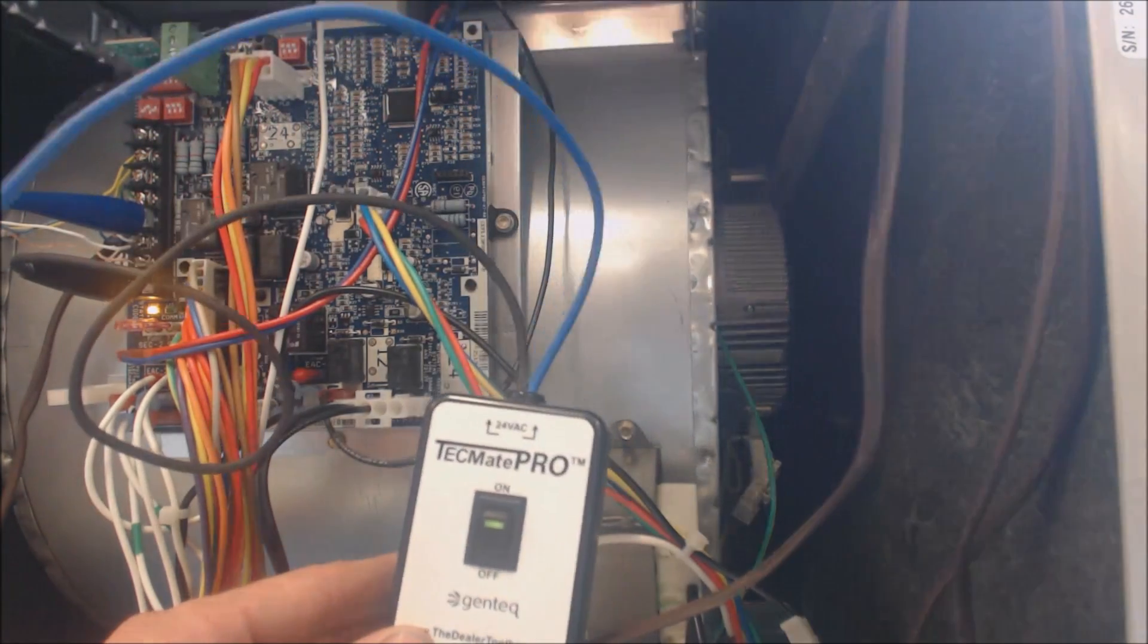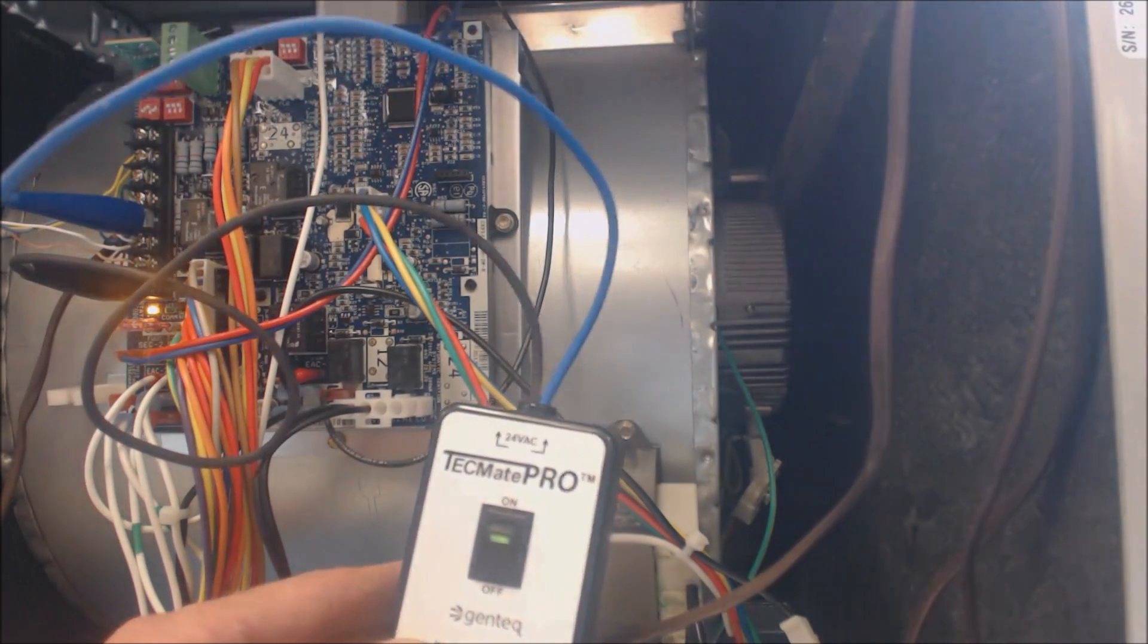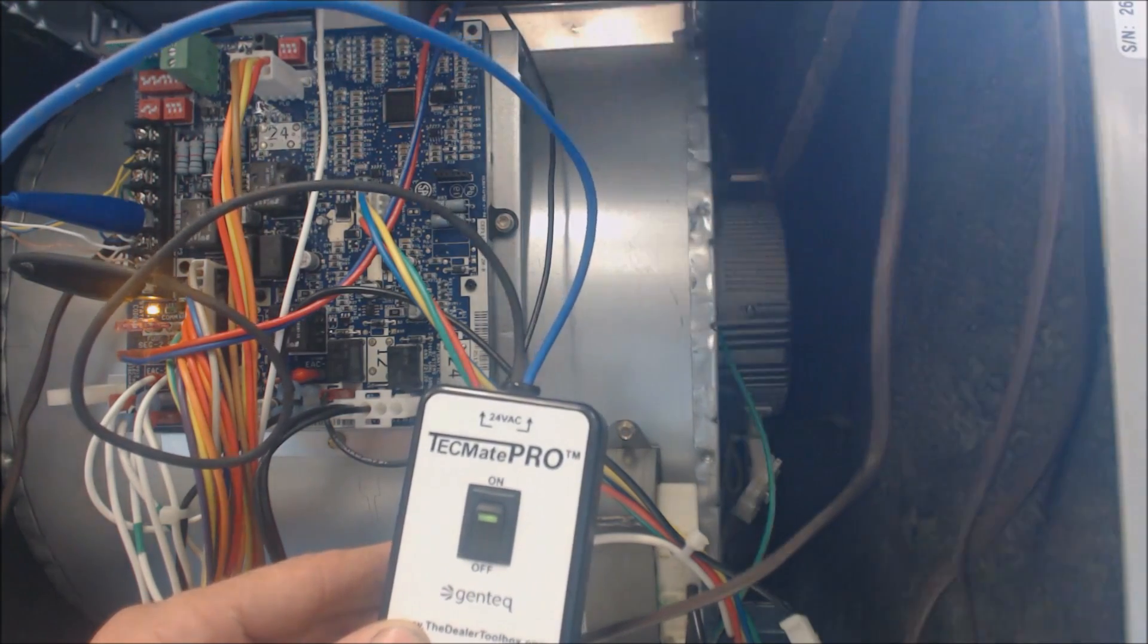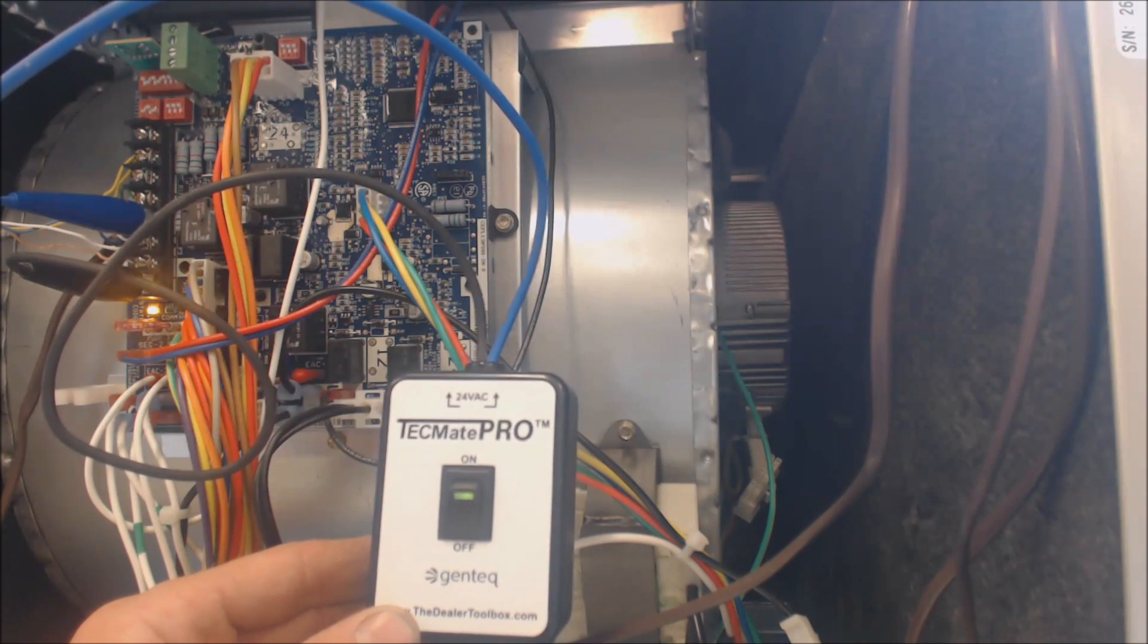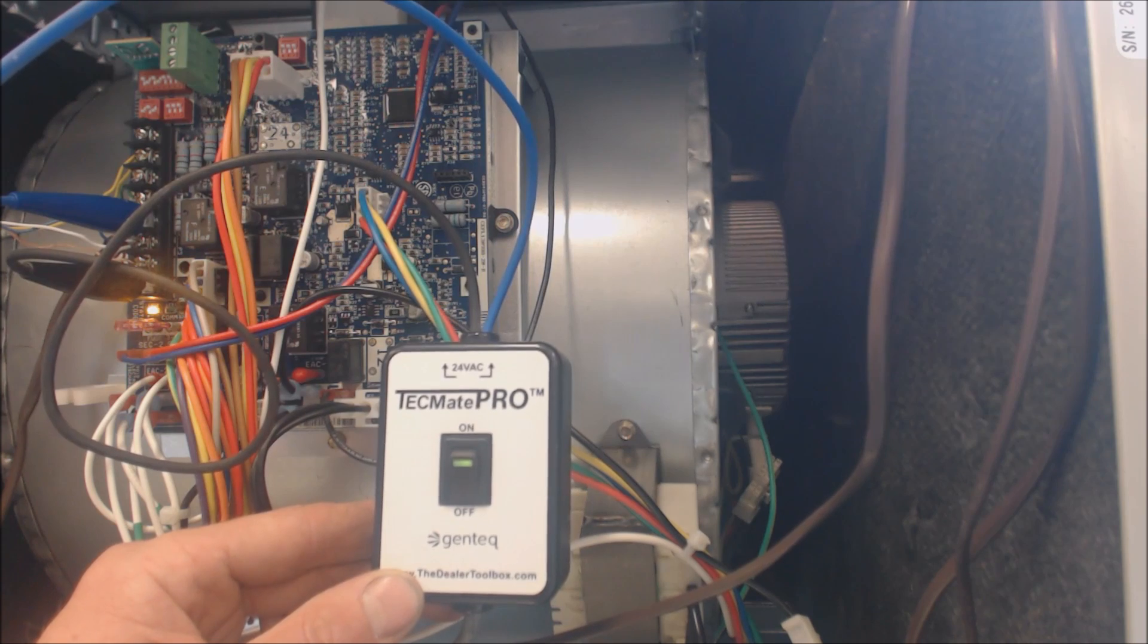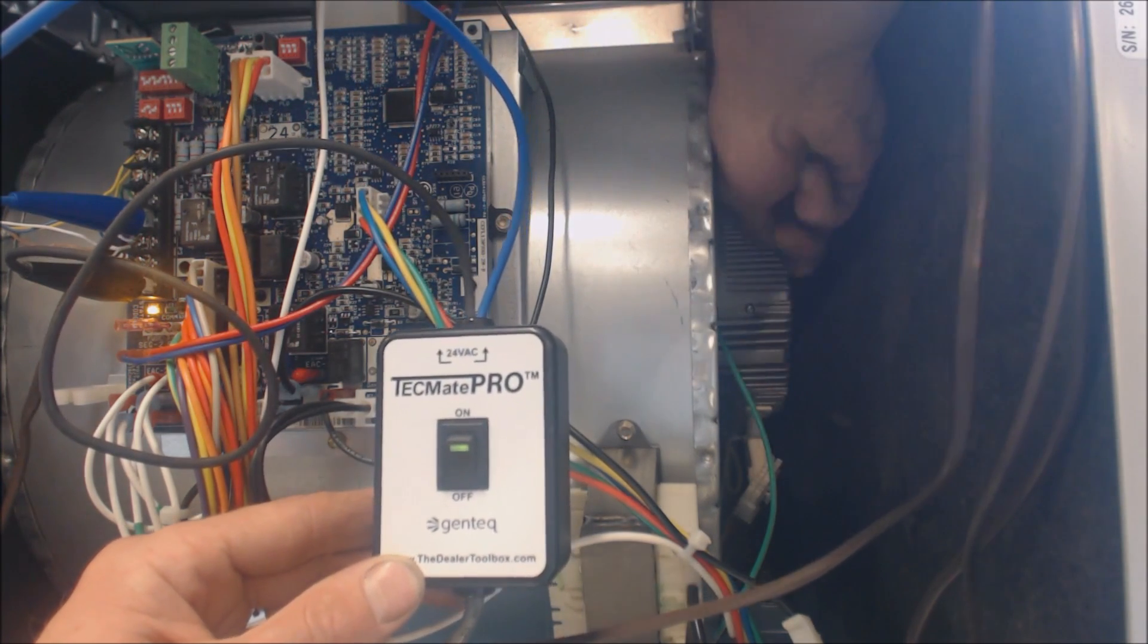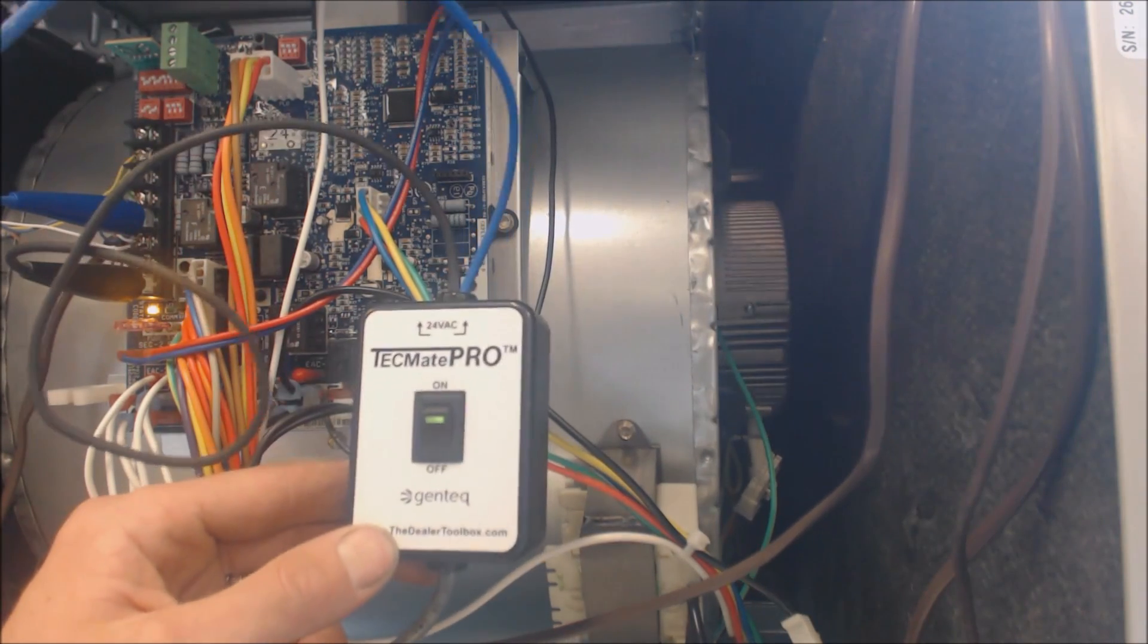And just for your reference, when you replace a variable speed blower motor like this, you want to make sure that the electrical connections are on the bottom, not on the top. Because just say the evaporator coil was to freeze or something for some reason - maybe low refrigerant charge - you don't want the water to drip down onto the top of the blower motor.